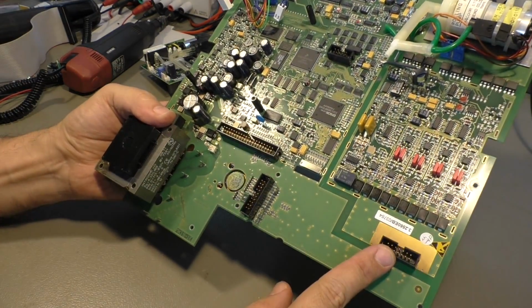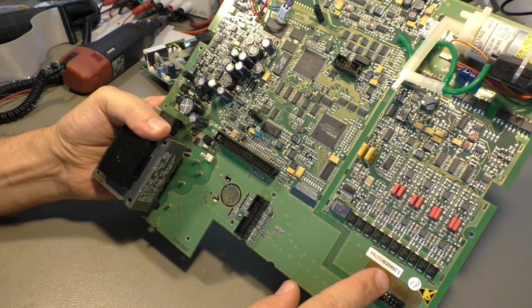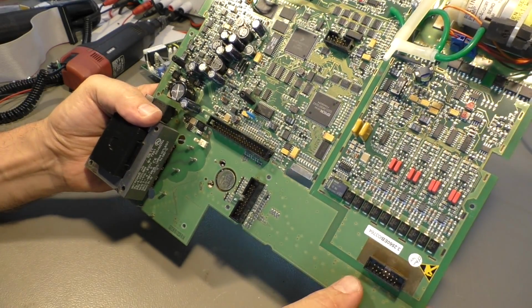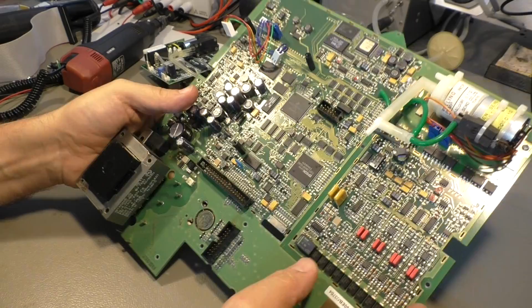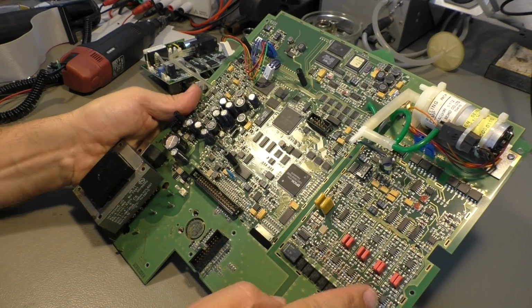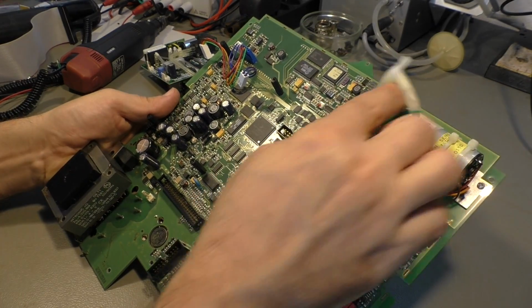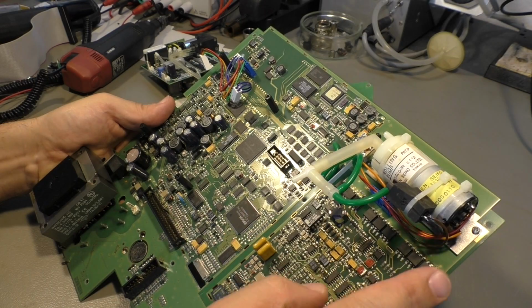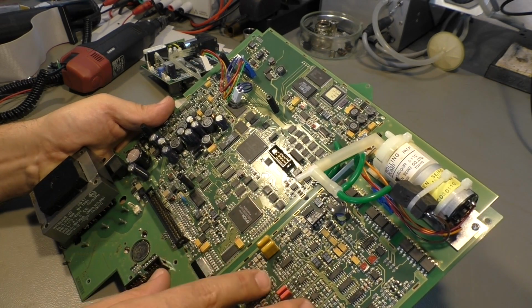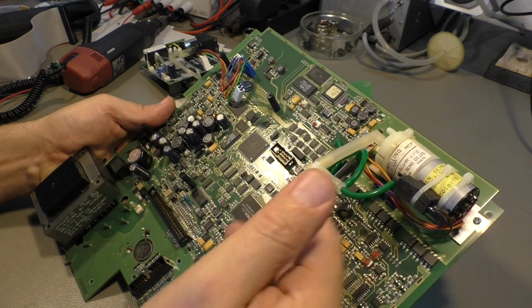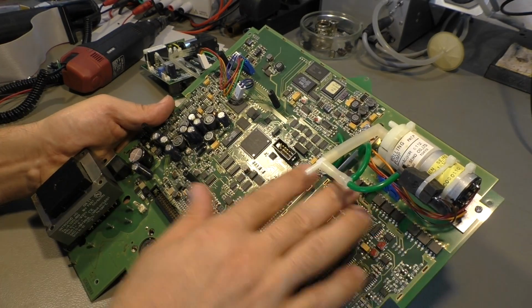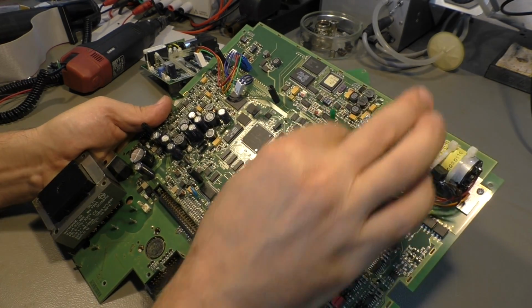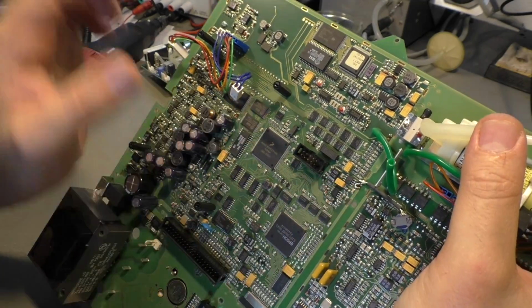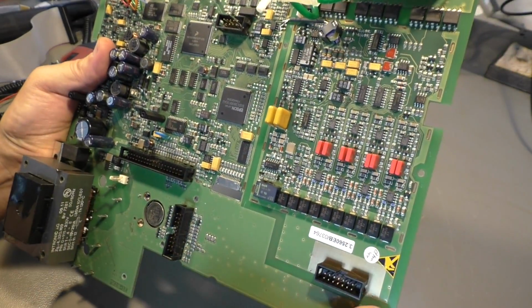We have here 12 channels in total. Most of the time you only use 3, maybe 5. The rest of it is like an oscilloscope, a very slow one. There are input amplifiers, input filtering, everything of course with optocouplers, not only to protect the unit from these electric shocks, but also to protect the patient if anything goes wrong inside here. Everything is totally electrically insulated. Even this little transformer here with a wire to the other side. Insulation gap all around. Total insulation also on the back side here.